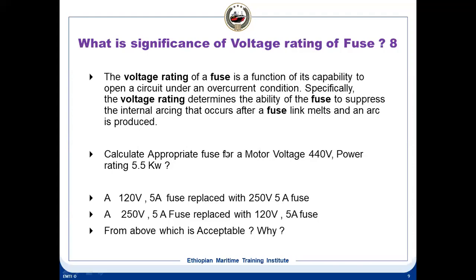The voltage rating is very important because the voltage rating specifies the gap between the electrodes where you have the fuse element. So that is why you cannot replace a higher rated fuse with a lower rated voltage. Okay, so the correct one is you can replace 120 volt with 250 volt, not 250 with 120.